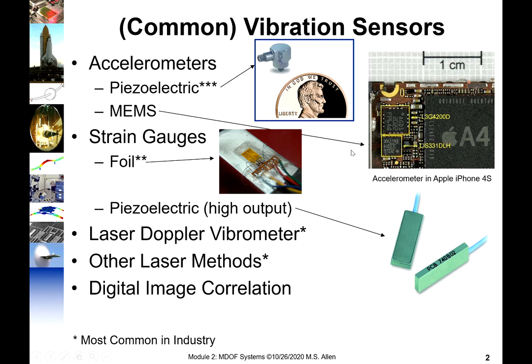Another common vibration sensor is a strain gauge. Assuming you've learned about this in a different instrumentation class, basically you stretch a resistor. The strain gauge is a foil resistor, and when a beam flexes it stretches, changing a voltage in a circuit that's converted into a strain signal. There are also piezoelectric strain gauges, which use stretching of a piezoelectric crystal to create voltage rather than changing resistance, giving them much higher sensitivity — maybe a thousand times higher.